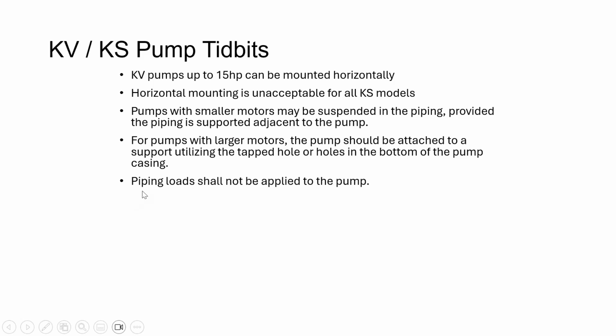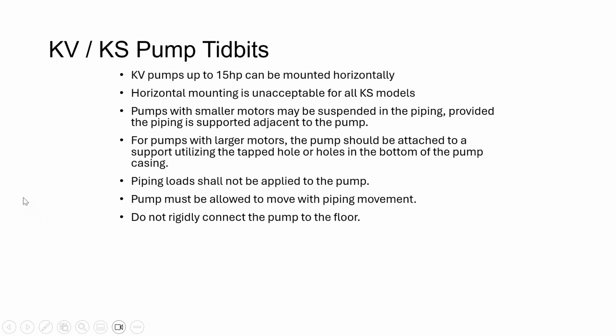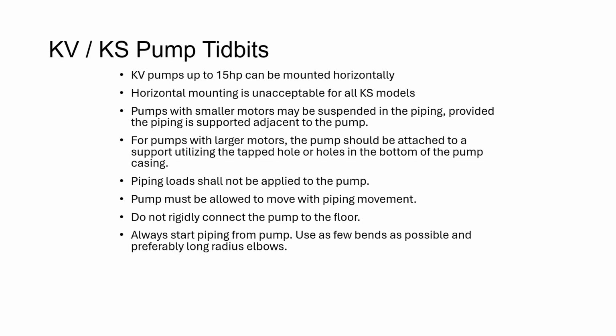Yeah, and this is for all pumps. Piping load shall not be applied to the pump. I can't emphasize that enough. Shall not be applied to the pump. It's just going to mess things up drastically, right? Pump must be allowed to move with the piping movement. Pretty straightforward there. So do not rigidly connect the pump to the floor. When you put that stand on, you just let it rest there, and I'll show you some of the recommendations for mounting these as well.